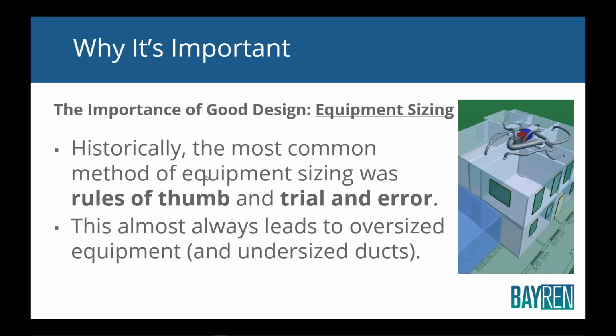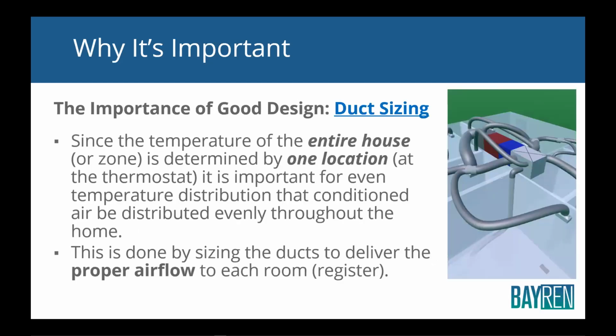All right. So let's see. Historically, the most common method of equipment sizing was rules of thumb and trial and error. If they just say, oh, let's do the 500 square feet per ton, and then they undersize the ducts and it's just not working well and the homeowner complains, they'll say, oh, well, on the next house, let's bump it up half a ton. And like I said, that's just leading to oversized equipment and undersized ducts. And that's a very bad combination. That's where you're going to get a lot of the complaints, a lot of humidity issues, a lot of uneven temperatures throughout the house and things like that.